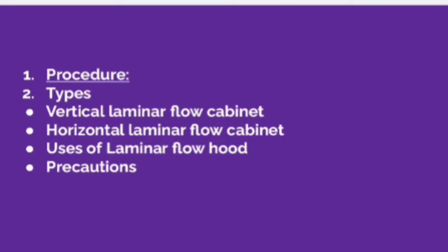The filtered air is then exhausted in a horizontal direction to the workplace environment. One advantage of this cabinet is that airflow parallel to the workplace cleanses the environment with a constant velocity. The effluent air directly hits the operator, which might reduce the security levels of this type of laminar airflow cabinet.